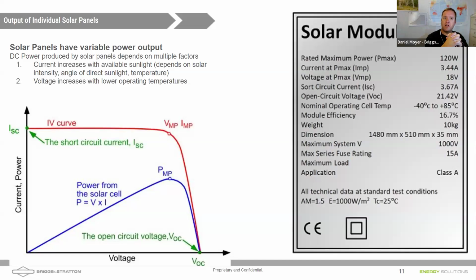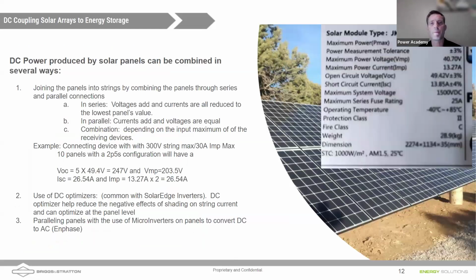Those voltages are important to keep in mind, especially in the context of DC coupling. A lot of these maximum power point trackers have certain voltage ranges, so you need to wire enough modules in series to build up the voltage so that you're above the MPPT startup voltage, but not exceeding the maximum voltage that MPPT can handle. I've also noticed, Nathan, that these ranges are getting much larger. Some of these MPPTs can go up to almost 600 volts now. Yeah, and the Sol-Ark that we'll be talking about, the operational voltage is up to 500. The maximum open circuit voltage of your arrays on the 3 MPPTs is 550 volts. Some of the smaller charge controllers that I'll show here in a minute have lower overall string voltages.